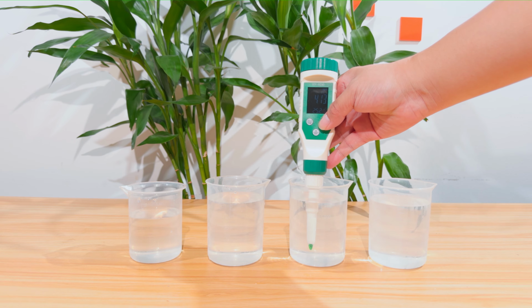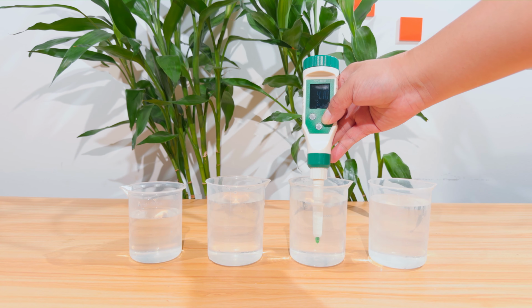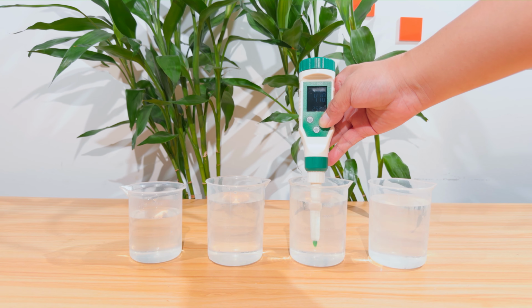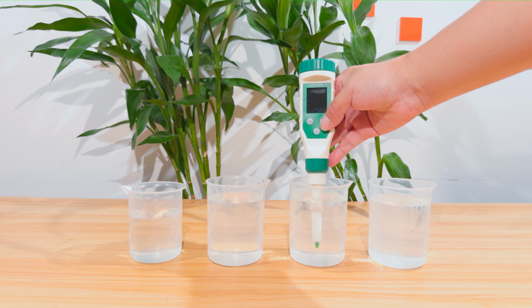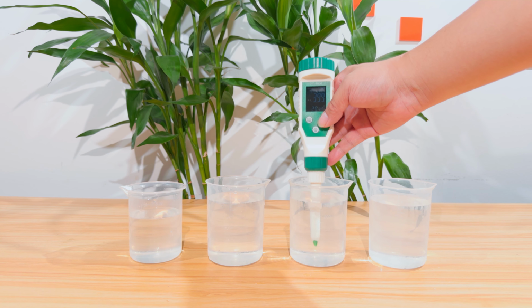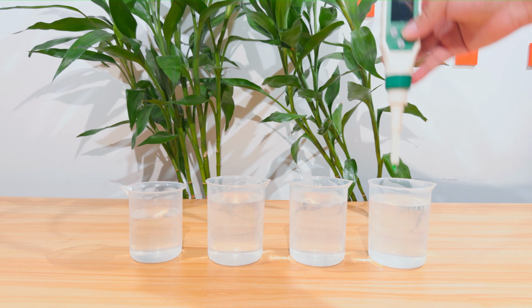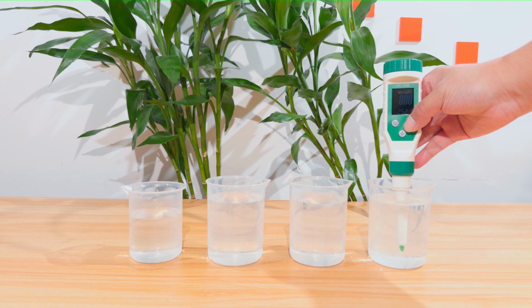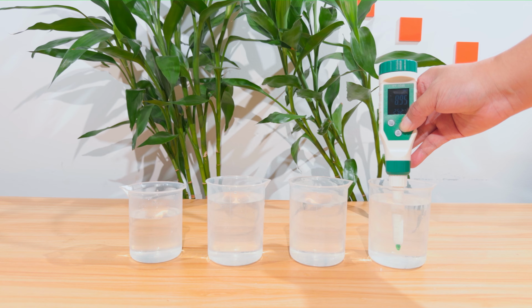Next, press and hold the cal button for 6 seconds to calibrate for 0.0. The screen will display cal and flash for 0.0. When the flashing stops, calibration is complete. Rinse the electrode again. Finally, press and hold the cal button for 6 seconds to calibrate 9.18.